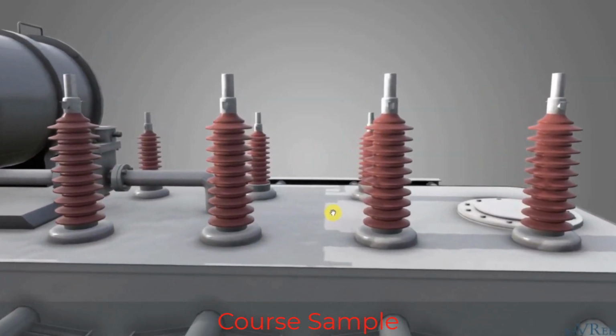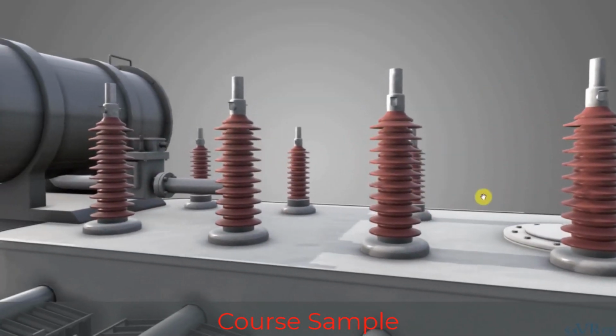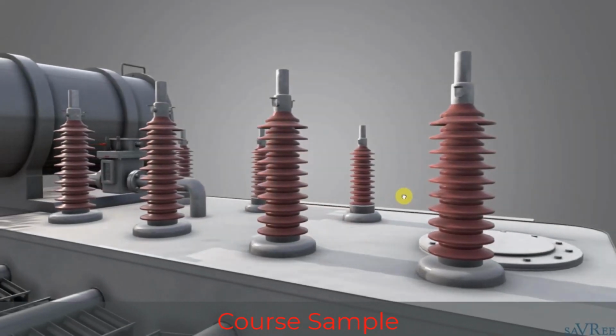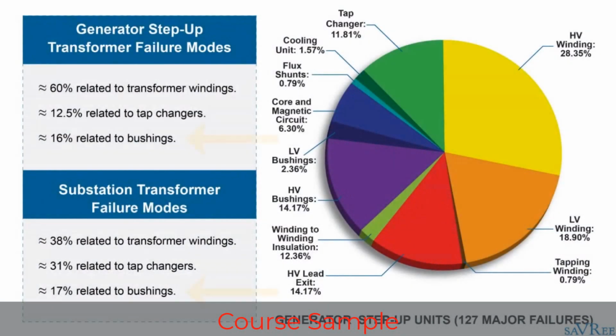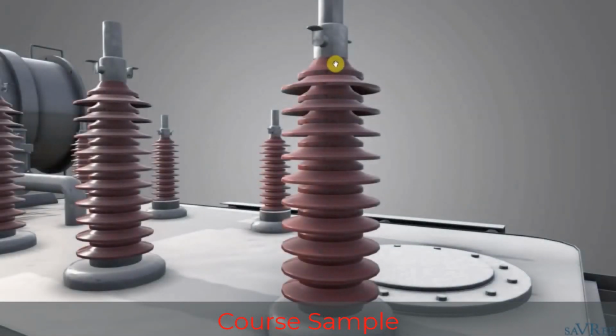The bushings are a common failure mode for electrical transformers. I believe they're in the top 3 failure modes for transformers. So pay attention to the bushings, look at the condition, look for any signs of cracking on the bushing, any signs of dust accumulation, and any signs of scorch marks or dark areas where the bushing might have been heated up considerably.